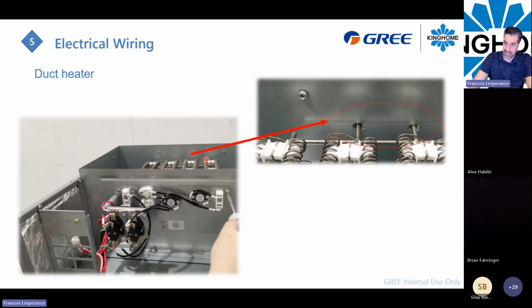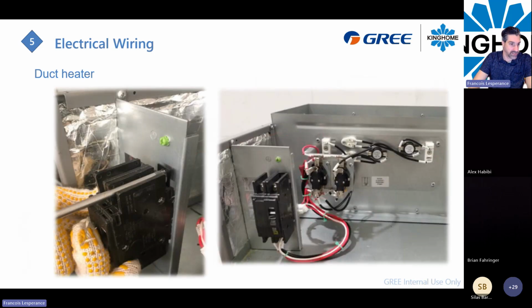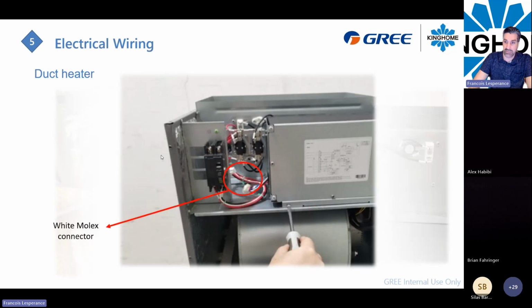So at the far end here in the cabinet, you will have 2 small holes right here just to push the brackets in it to hold the duct heater correctly. So that's really important. So this is why, you know, here the top panel needs to be removed if you want to have enough space to install this kind of duct heater. And so on the other way here, you will have a breaker, so that can be installed. So as a reference, this one is a 10 kilowatt, so it's using only 1 breaker. If you have more than that, maybe you will have a 15 or 20 kilowatt. So in my region right now, most of the time it's 15 or 20 kilowatts. So we always use a double breaker assembly here and a single point kit. It's all available. But for the reference in that picture, it's a 10 kilowatts, so we're using only 1 breaker.